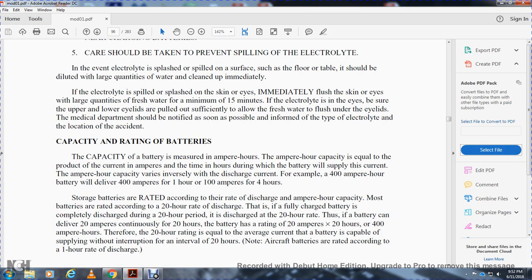Capacity rating of batteries: battery capacity is measured in ampere-hours. Ampere-hour capacity equals the product of current in amperes times time in hours. Capacity varies inversely with discharge current. For example, a 400 ampere-hour battery will deliver 400 amps for one hour, or 100 amps for four hours. Most batteries are rated according to a 20-hour rate of discharge: a fully charged battery is completely discharged over a 20-hour period. Thus a 400 ampere-hour battery rated at the 20-hour rate can consistently deliver 20 amperes for 20 hours.